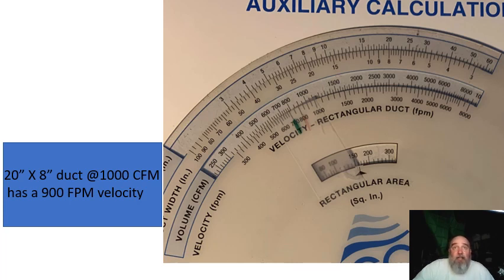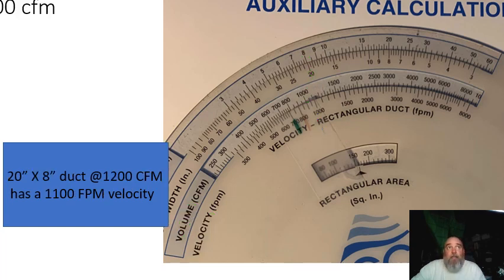The auxiliary calculator on the back of the ACCA duct slide gives us some guidance here. My example is 20-by-8 ductwork at 1,000 CFM — it shows us that 20-by-8 ductwork is going to have 1,000 CFM flowing through it and the velocity is going to be 900 feet per minute. In the example where we have 20-by-8 ductwork trying to support 1,200 CFM — which is our target from equipment selection — if we're trying to move 1,200 CFM through it, we're going to be at 1,100 feet per minute.